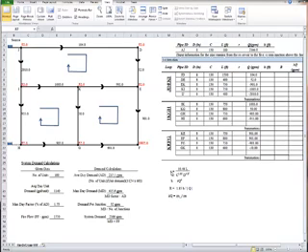It's the lowercase r, and it's shown as 10.48 times L over C to the 1.85 times D to the 4.87. So we'll start with that calculation for pipe AJ, which goes to the reservoir down to the system. So I'm just going to type in here equals 10.48 times the length divided by C value to the 1.85 times the D value to the 4.87.